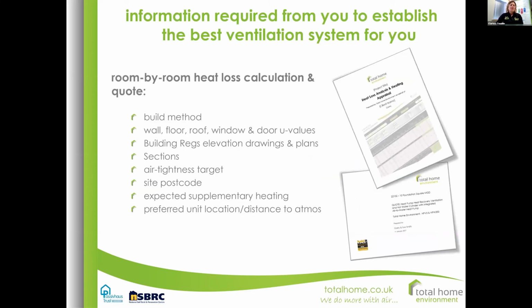So information that we, for instance, would need to establish what ventilation system is going to be best for you is what your build method's going to be, to get this room by room heat loss calculation done and a quote done. And we'd want to know your U values for wall, floor, roof, windows, doors, etc. And building regs drawings would be very useful, rather than just something slightly earlier. We need sections to work out the volumes. We'd like to know if you've got an air tightness champion on site, what sort of air tightness target you're going to get to, obviously your postcode, and any sort of towel radiators and things like that that you might be having.